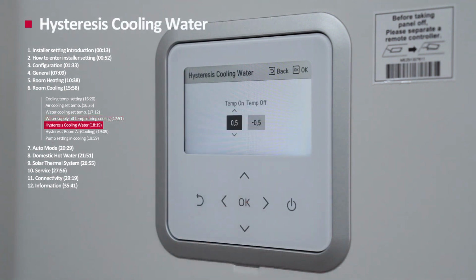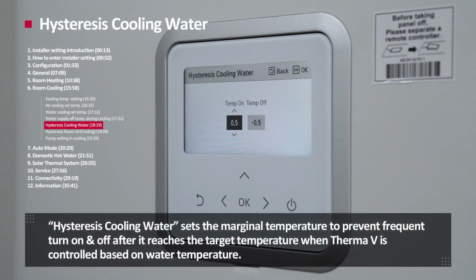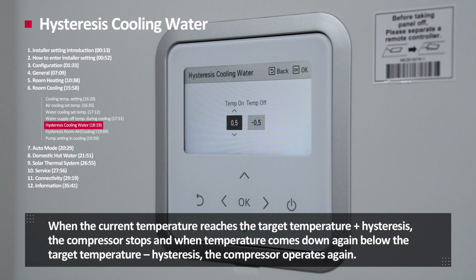Hysteresis Cooling Water sets the marginal temperature to prevent frequent turn on and off after it reaches the target temperature when Therma V is controlled based on the water temperature. When the current temperature reaches the target temperature plus hysteresis, the compressor stops. And when temperature comes down again below the target temperature minus hysteresis, the compressor operates again.